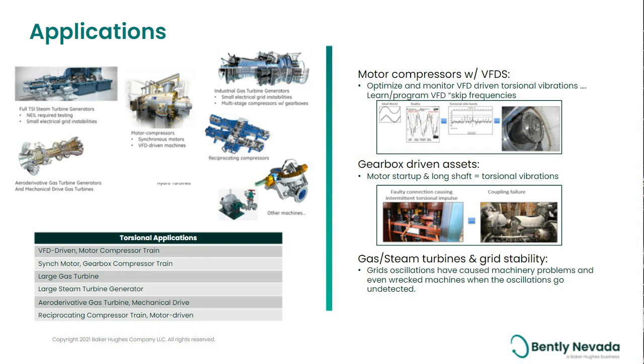And then last but not least, and again, not all inclusive, one other key example we've seen is certainly typically in the power industry here, where you've got grid instability. So this is basically a prime example would be you've got a power generator on base load. There could be some auxiliary power coming in, whether it's from renewables that hits the grid. The entire grid system looks to, again, dampen out those vibrations coming through on the entire system. These vibrations or these grid oscillations, if you will, can cause havoc and can excite resonances even in large steam generators or gas-driven generators.